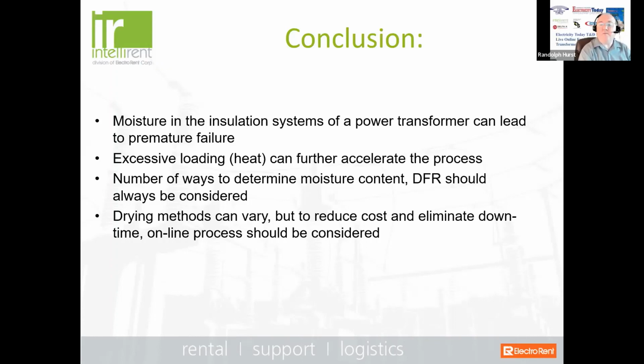Okay, what is the best time of the year to take oil samples from a transformer, especially from a moisture point of view? Well, the best time is when it's convenient for you to take your transformer offline. And that's important. And this is a problem that we're seeing right now, because of the excessive load that the excessive heat throughout the country is causing. I was in a working group meeting on Monday this week, and I'm on a working group that's dealing with setting standards for transformer monitoring. And a comment was made by one of the members that nobody's taking their transformer offline.